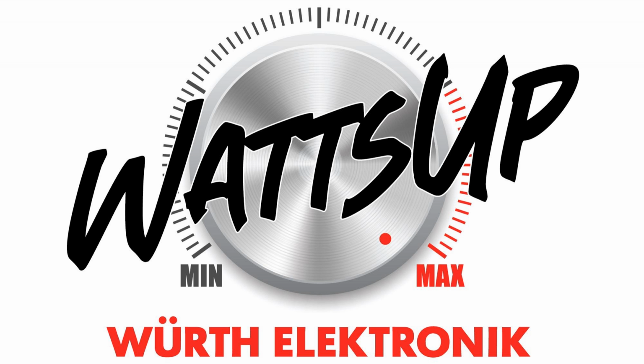We found that as soon as we take out this potting material, look what happens with the same construction, just the same transformer without potting material. We passed the EMC test. So because of that, we decided not to increase the dielectric in the transformer and not to use varnish or potting material in the transformer, because that may also cause some negative EMI effects and noises.